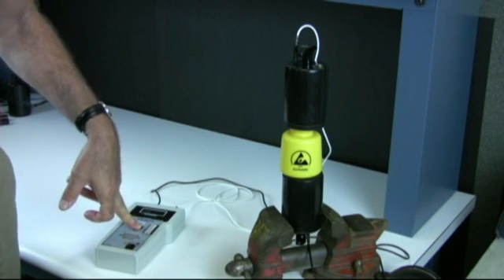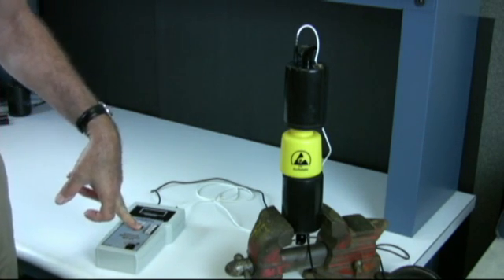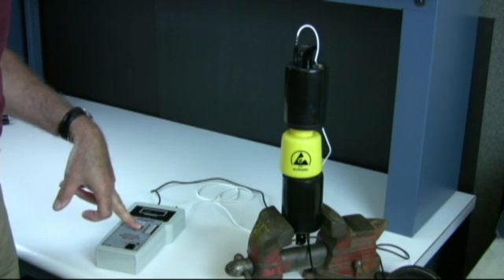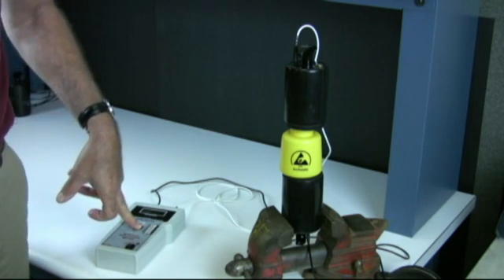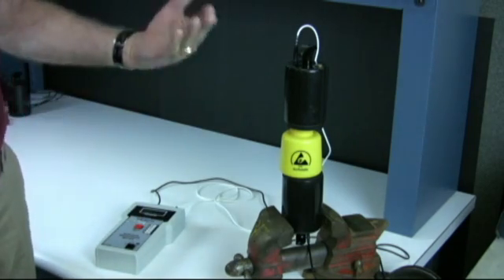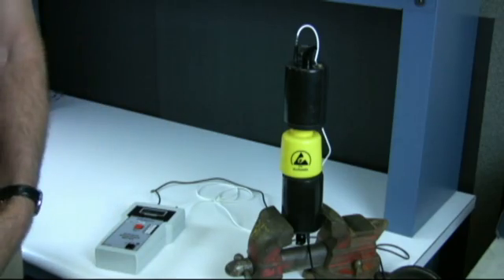It gives me other bits of information, but I'm waiting for it to determine that it will measure at 100 volts. The result is 1.2, 1.3 times 10 to the eighth ohms. It's a fairly quick test. This is measuring volume resistance through this bottle, and this one is a good one.